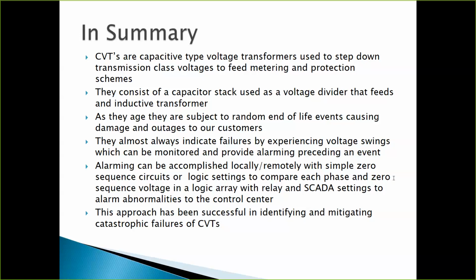Excellent question. Do the accuracy of CVTs vary with time? That's a fantastic question. I'm glad you asked that. So this is old school. The CVT's been around a long time. The old CVTs used a cellulose paper that provided the insulation between the capacitor elements. So over time, absolutely, they varied. This is your 70s and 80s vintage CVTs, absolutely vary with accuracy. It was a problem. You saw very few metering applications back from the 70s and 80s because the meter guys complained.